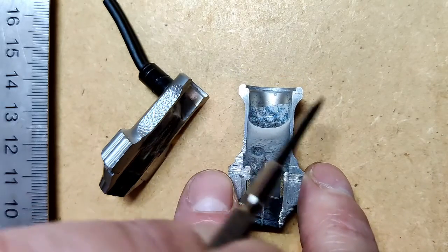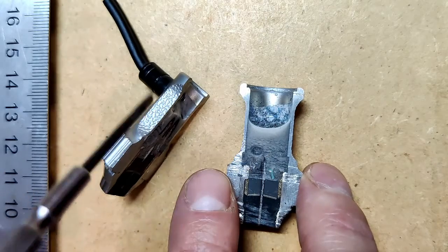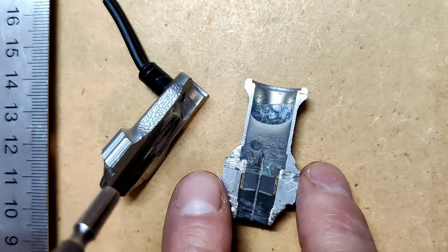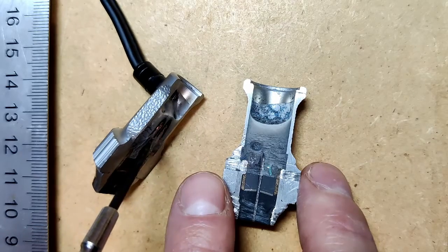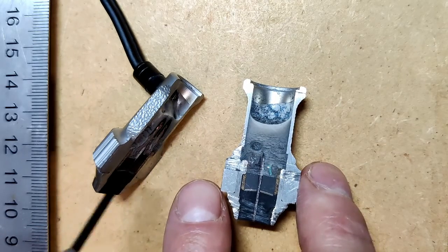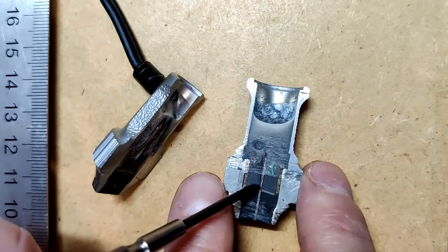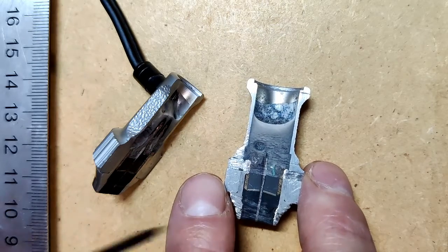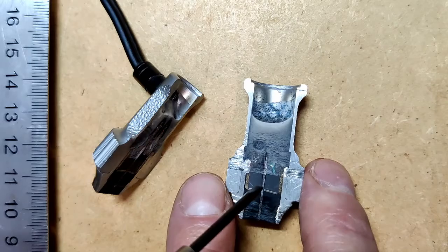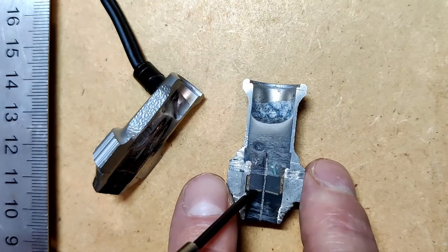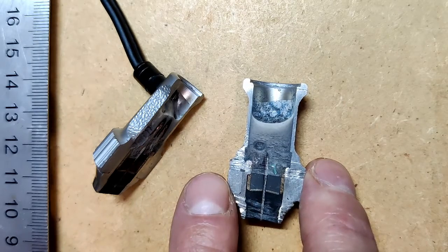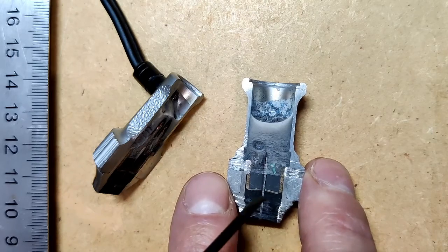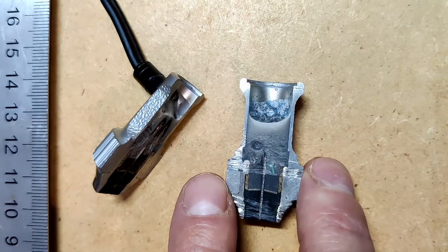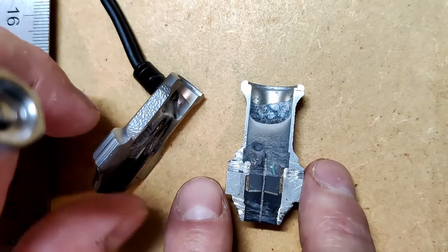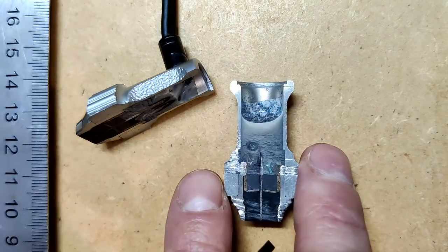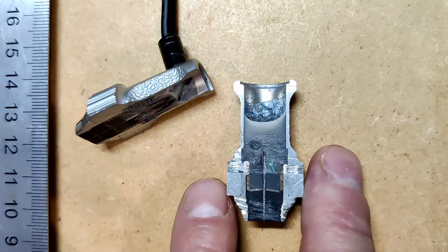We've got the external housing that we can see over here and here and here. The cables run down through the housing and would connect onto either end of each one of these crystals inside. So we can see the backing material that the crystals are set on, generally an epoxy resin type material, which is designed to dampen the ultrasonic signal that we generate once we excite these crystals and create our sound wave.